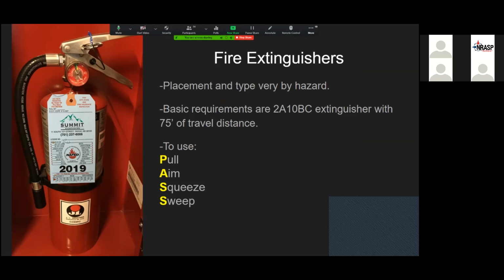Another way, active fire suppression, fire extinguishers. You see them all throughout your facility. Placement and type vary by hazard within the fire code, but the basic requirements are for a 2A 10BC fire extinguisher located within 75 feet of travel distance anywhere in your facility. So that's what most requirements will fall under for your facility. But if you have a special hazard, you may have to ask your fire department if they have a different fire extinguisher that's required, or if the travel distance is different.